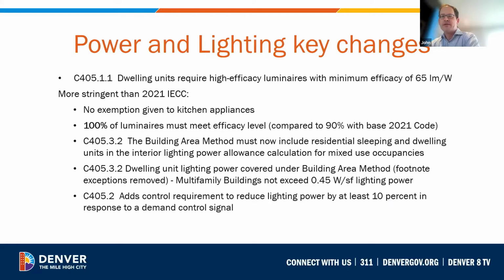The building area method in C405.3.2.1, which is contained also in the IECC, provides a simple way for projects to comply with lighting requirements using a simple watts per square foot allowance for the entire building. The Denver Energy Code removes the exceptions for residential occupancies when using this approach, the building area method, for lighting compliance. For example, multifamily lighting power allowances of 0.45 watts per square foot and the dormitory lighting power allowance of 0.53 watts per square foot would apply to all spaces, including dwelling units. If a building has difficulty complying using this approach, it can comply using the space-by-space approach. The code also includes a new control requirement for dimming by at least 10% in response to a demand response signal.